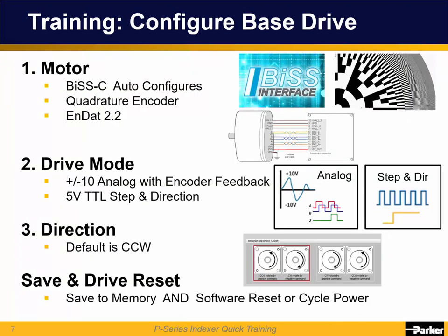When you're ready to configure the drive, there are three main settings: the motor, the mode for the drive, and the direction. The P-Series motors and the new MPP with BiSS-C automatically send the motor information to the P-Series drives on power-up. The MPP with BiSS-C needs firmware version 2.04 or higher but can be updated in the field.